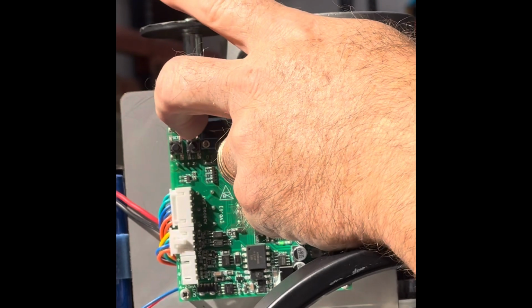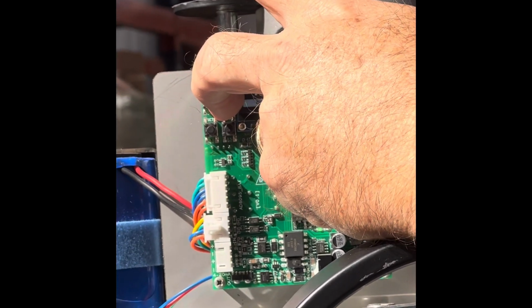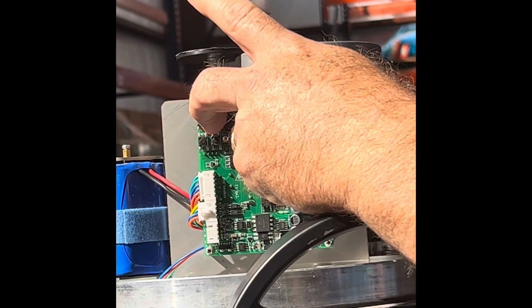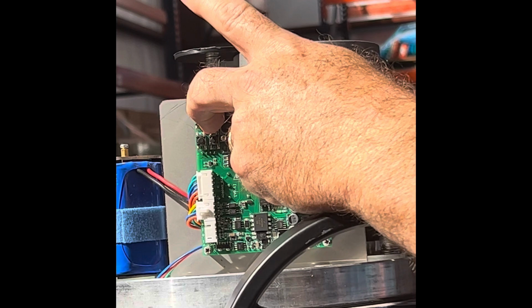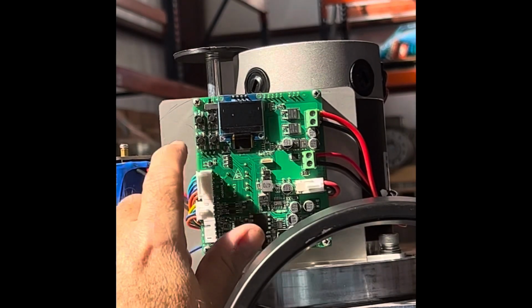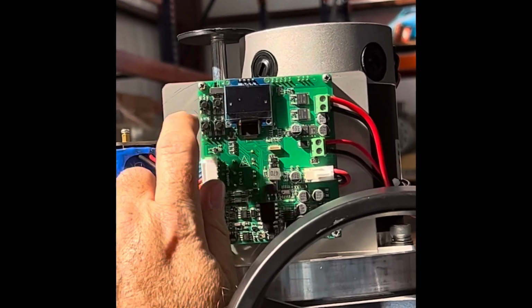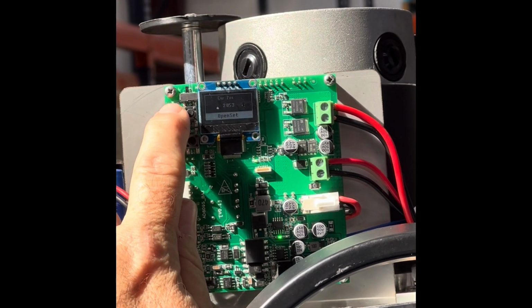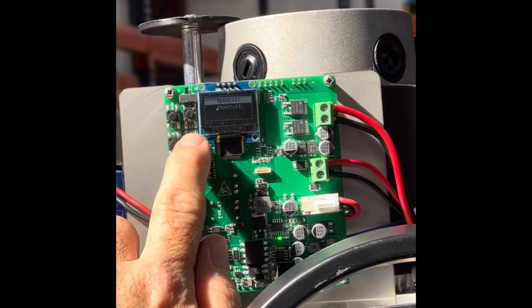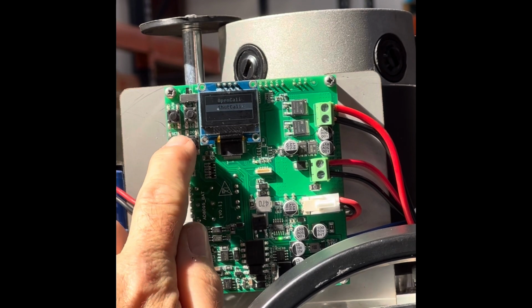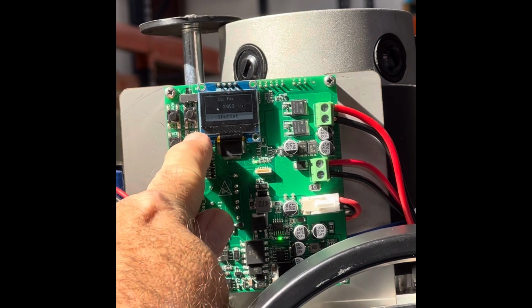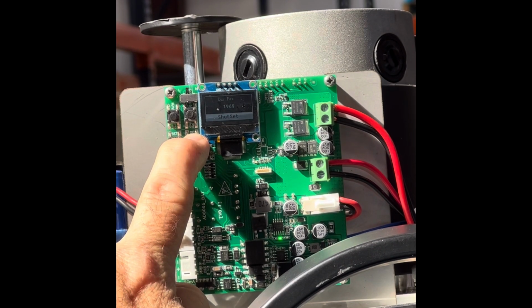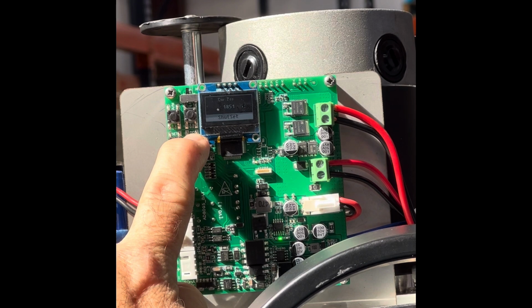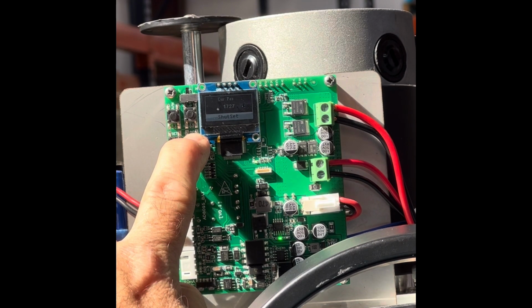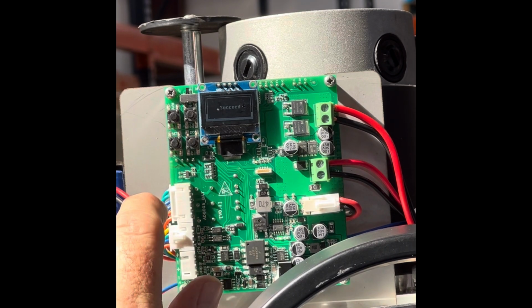Up is your open, up drives counterclockwise. So press and hold it until you like where your open position is. Okay, and then hit set. And then it says succeed. Then you hit the top left, go back again. Now you're back at open cal or shut cal. Go down, press set. Now press the down button. Calibrate the close. Okay, then hit set there.